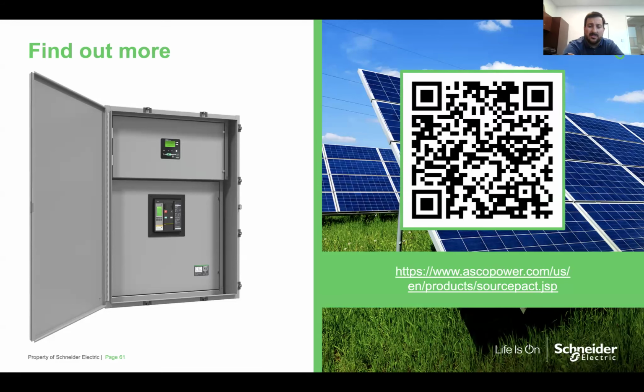Exact solution depends on the architecture in the one line, but from what I'm reading, and again, making a lot of assumptions here, we'd have to look at a one line and talk through it more. I think in this case, a standard transfer switch would actually work with your utility or the EV itself being the primary source of the ATS and the preferred source, but then having that microgrid be the secondary source. So utility fails, and as long as there's power on that secondary source, that ATS is going to switch over to that other building's microgrid. And then that would be feeding the load downstream, which is the EV chargers, right?